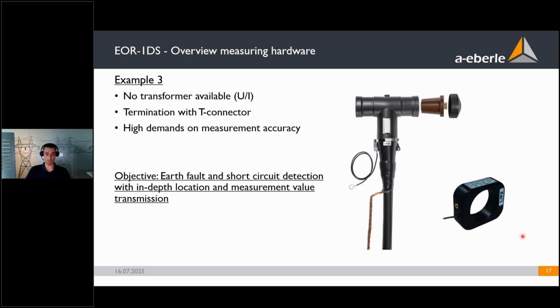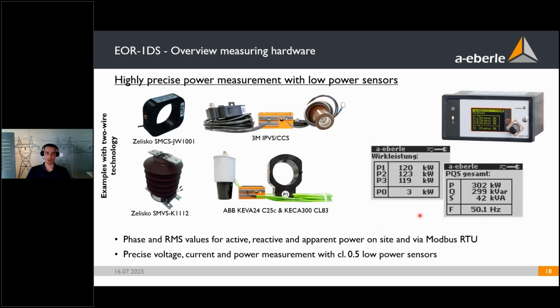The third example would be that you do not have transformers available, so no voltage and current measurement already installed, but you do have a termination with a T connector, and also you have high demands for measurement accuracy. The objective would again be to have earth fault and short circuit detection with in-depth location and measurement value transmission. For this option, you have the most precise measurement option. You have these highly precise power measurements with the low power sensors. For this, the EOR-1DS is compatible with a variety of sensor manufacturers, for example Zelisko, 3M, ABB, but also other manufacturers as well.